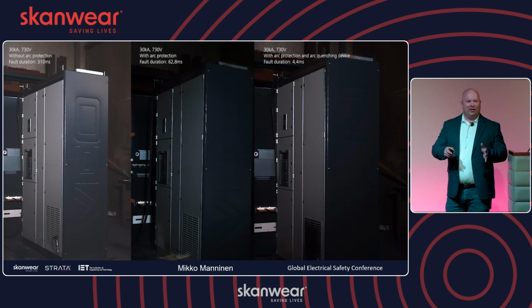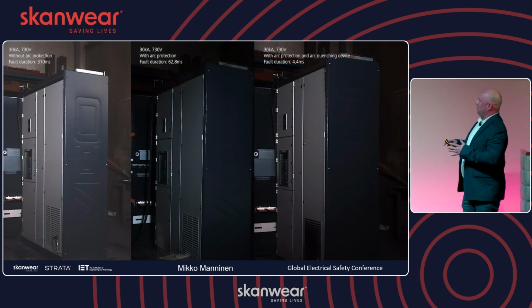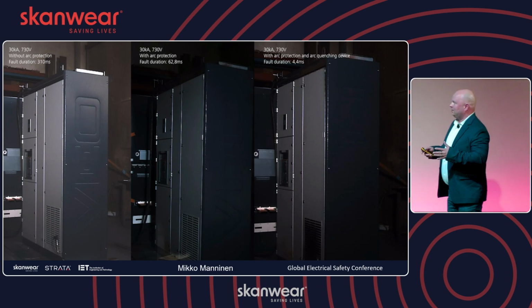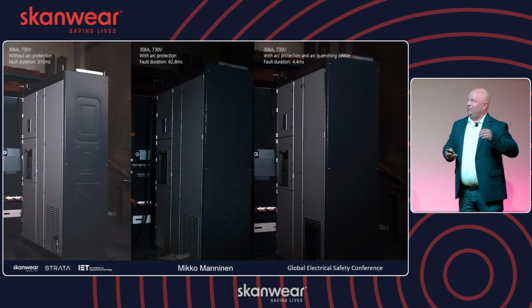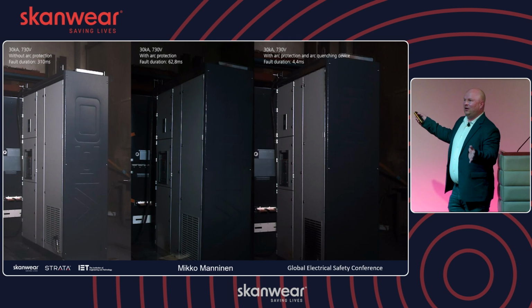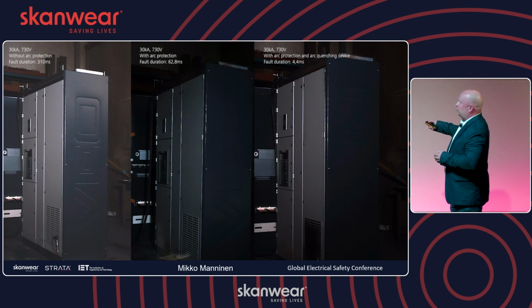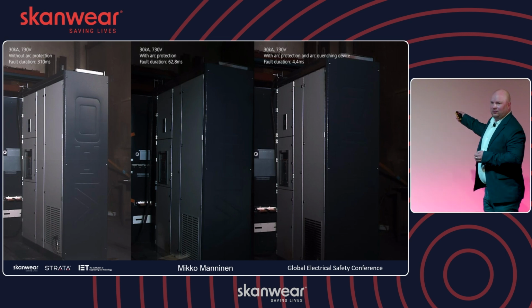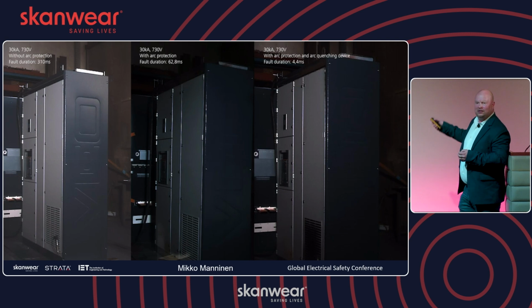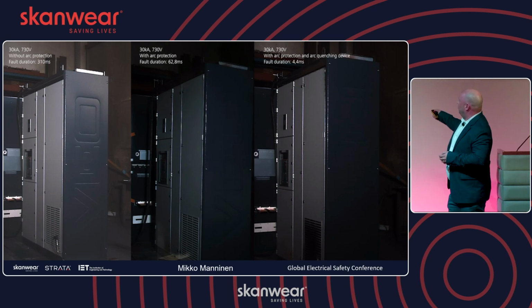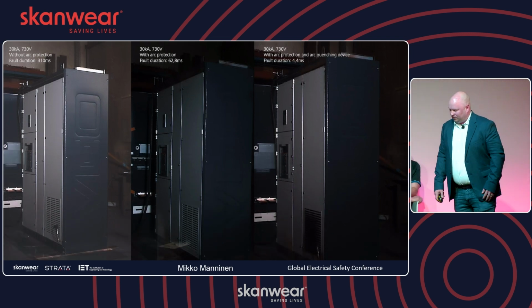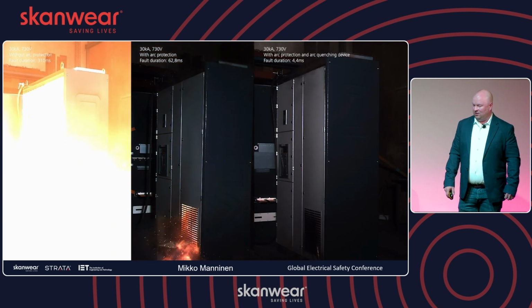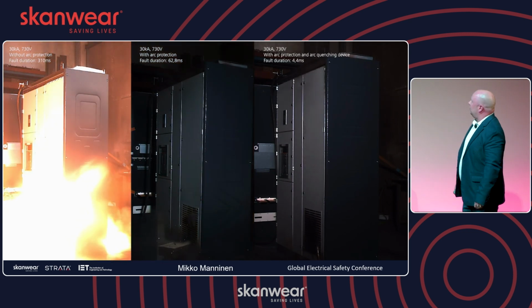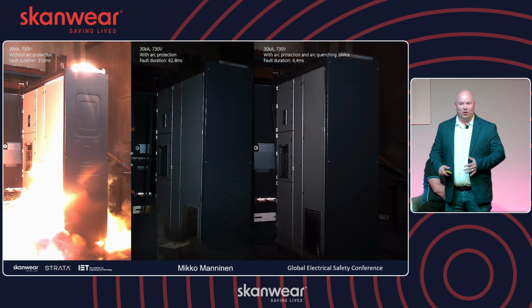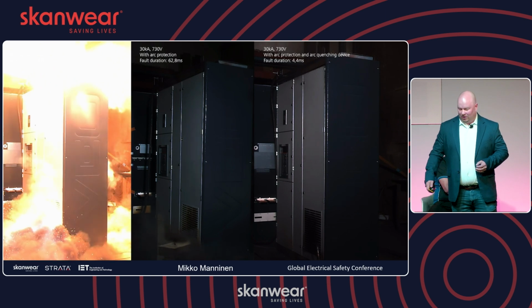So left side, this is a fully identical, fully synchronized video. Left side, you can see a 30 kiloamps, 730 volts arc flash. It's a simulation of the feeder protection upstream. The middle one, again fully synchronized, high speed, 1000 frames per second. This is an arc flash protection with the circuit breaker opening. And the right side is the arc quenching device. So have a look at this one because it goes quite fast. So again, high speed, 1000 frames per second. And yeah, looks like the left side is just about to start. So it will last quite long, so I will skip to the next one.